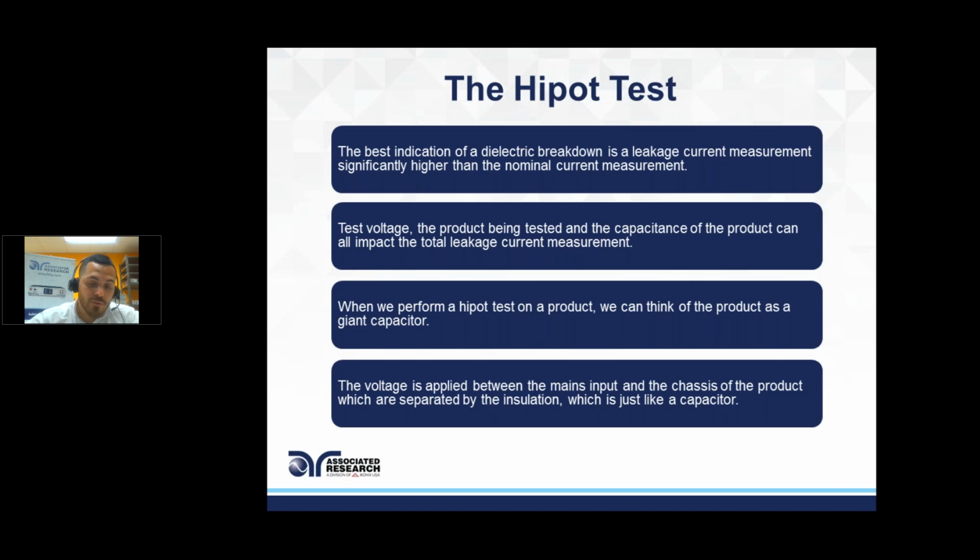right? So you've designed this product, you've developed it, you've gone through your performance phase, you're now in production phase. You've identified the characteristic of your product. You know it better than your operators do. You understand, yes, it does leak. Everything leaks a little bit, and some things leak a lot. You want to stay out of the "I leak a lot" category, right? And so setting your limits, which we'll discuss a little later in the slides, is a good way to develop uniformity among your products.